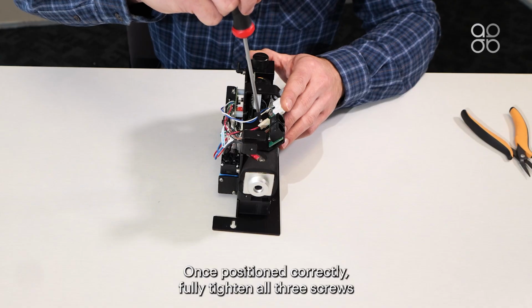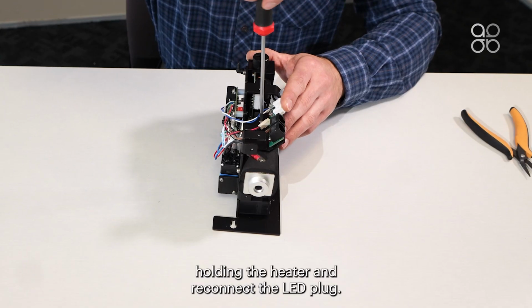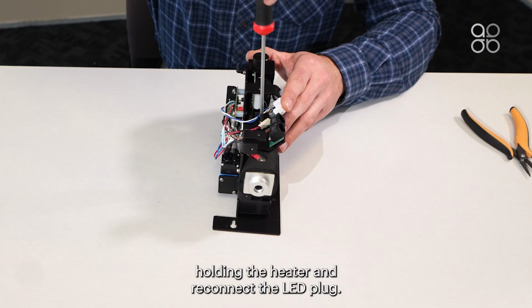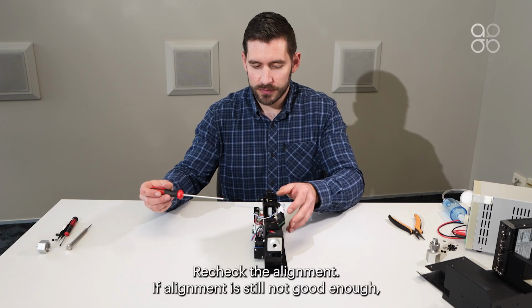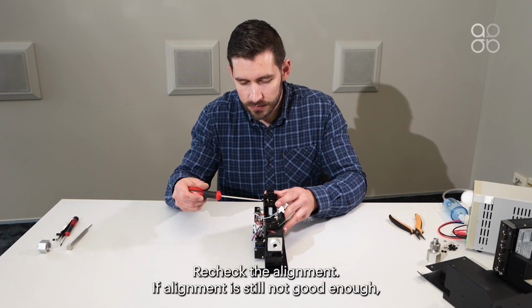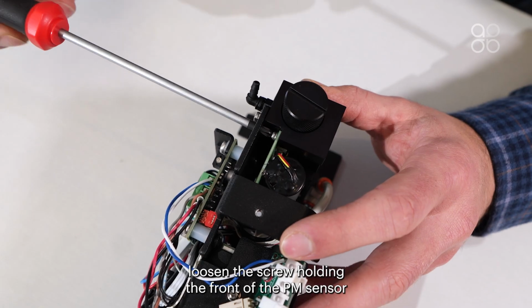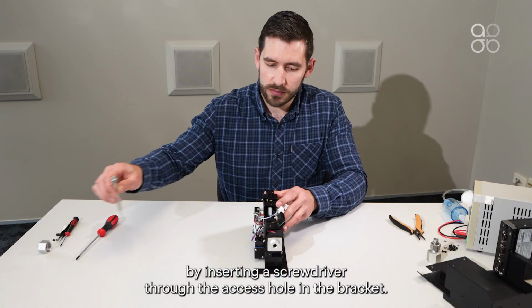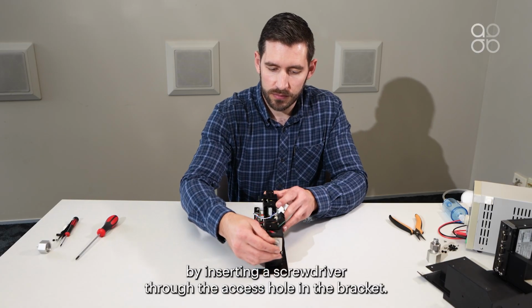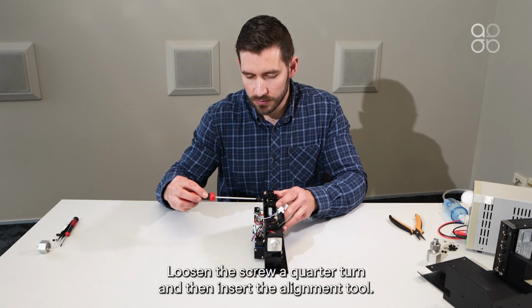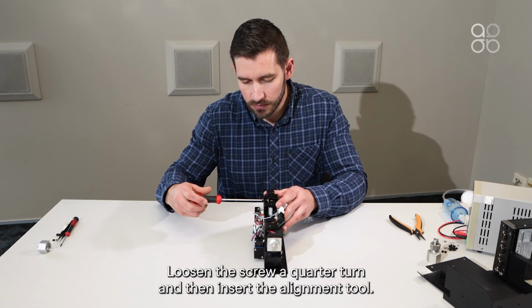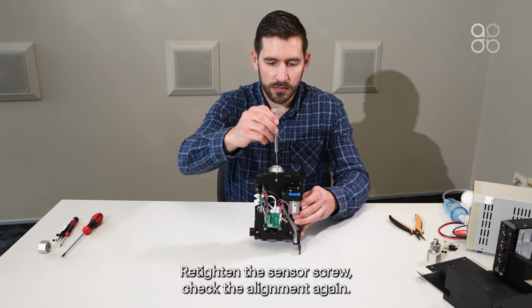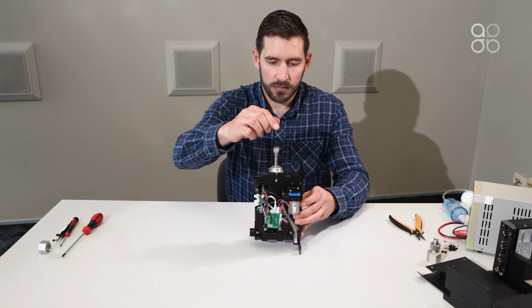Once positioned correctly, fully tighten all 3 screws holding the heater and reconnect the LED plug. Recheck the alignment. If alignment is still not good enough, loosen the screw holding the front of the PM sensor by inserting a screwdriver through the access hole in the bracket. Loosen the screw a quarter turn and then insert the alignment tool. Retighten the sensor screw and check the alignment again.